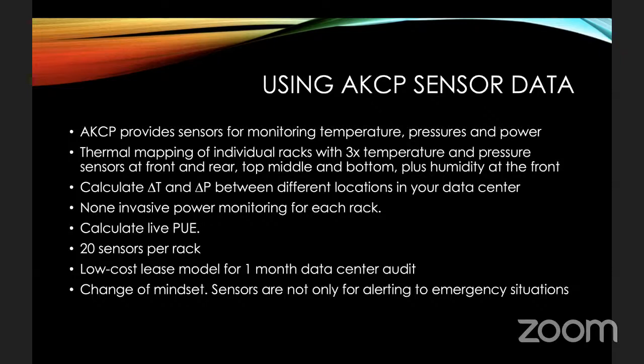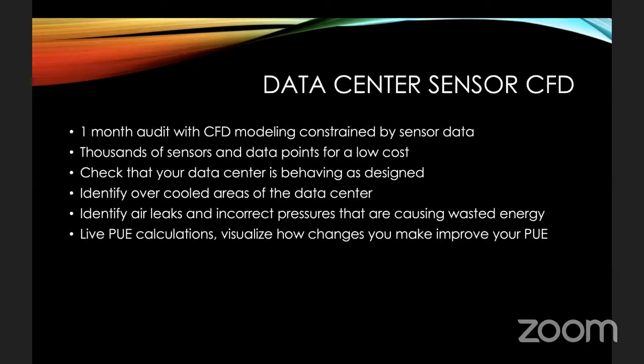So the sensors don't become just a method for alerting when there's an emergency situation. They become an actual tool that you can use to analyze the operation of the data center, improve the efficiencies, ultimately lowering your carbon footprint. So this is a 1-month audit with CFD modeling, constrained by the sensor data, thousands of sensor data points at a very low cost. You can check that your data center is behaving as it was designed. You can identify overcooled areas, identify air leaks, incorrect pressures, live PUE calculations, but it requires this change of mindset.